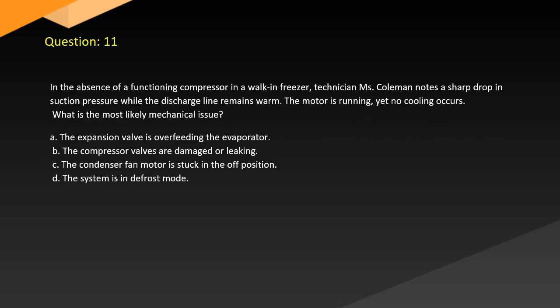Question 11. In the absence of a functioning compressor in a walk-in freezer, technician Coleman notes a sharp drop in suction pressure while the discharge line remains warm. The motor is running, yet no cooling occurs. What is the most likely mechanical issue? A. The expansion valve is overfeeding the evaporator. B. The compressor valves are damaged or leaking. C. The condenser fan motor is stuck in the off position. D. The system is in defrost mode.